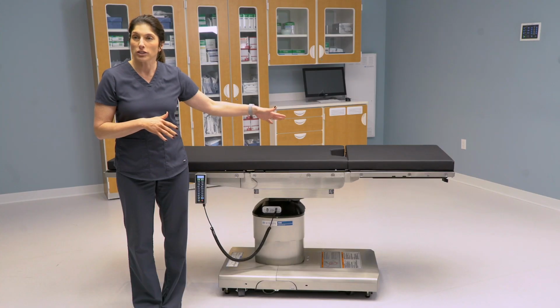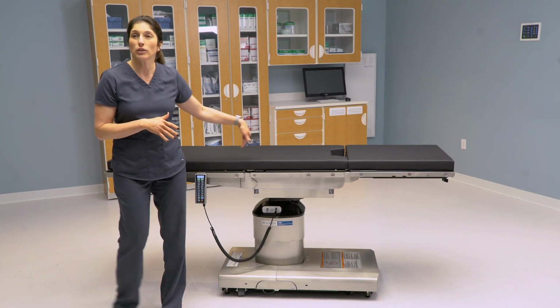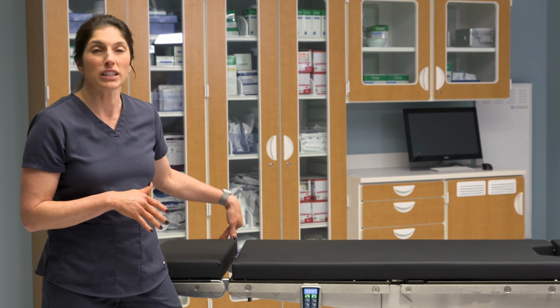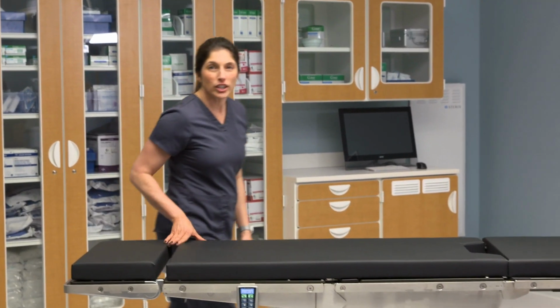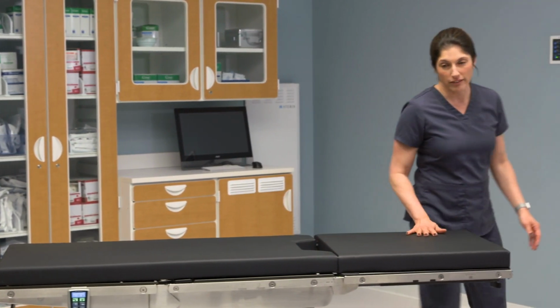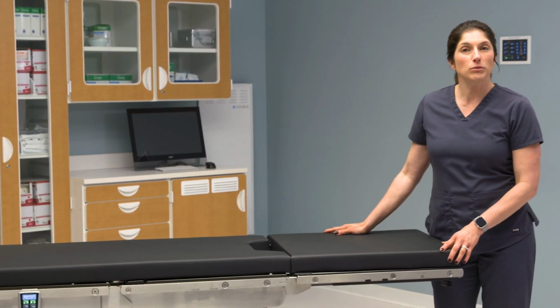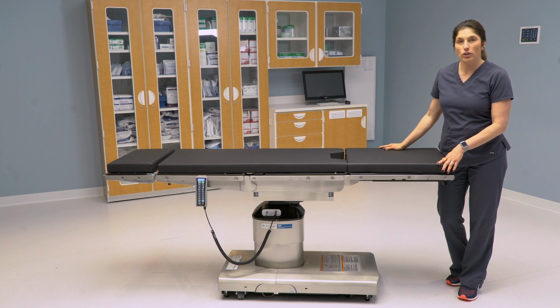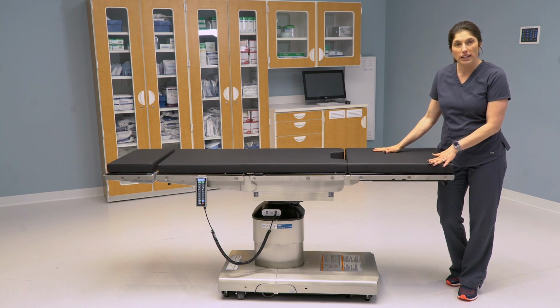You can slide the tabletop to the foot for 43 inches of lower body C-arm access, or you can slide the tabletop to the head for 43 inches of upper body C-arm access. Let's take a look at the removable leg section on the 4085. On the 3085, you're accustomed to lowering the leg section out of the way. You no longer have to do this. You have the option to remove the leg section.